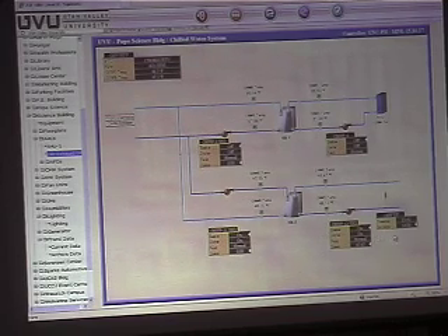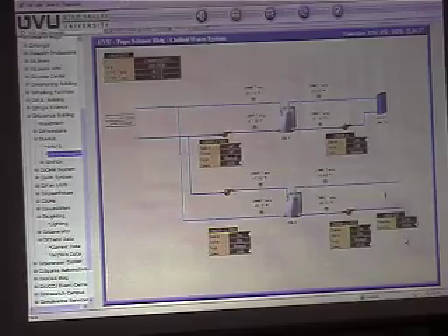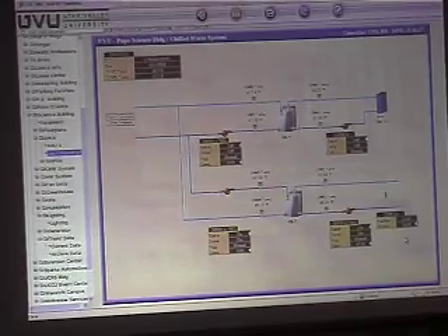So are there minimum requirements for that chilled water loop for the process controls? We're still waiting to find out what that is. The balancer gave me a differential right now to maintain at 14 pounds, but once they get the equipment in, that may be reevaluated and a different number may be set in there. Because what we get from the campus sometimes is, if the campus system isn't set up to be concerned about whether or not that loop has what it needs. Right. Yeah, I'm not sure yet what we'll have to maintain or what we'll have to provide.